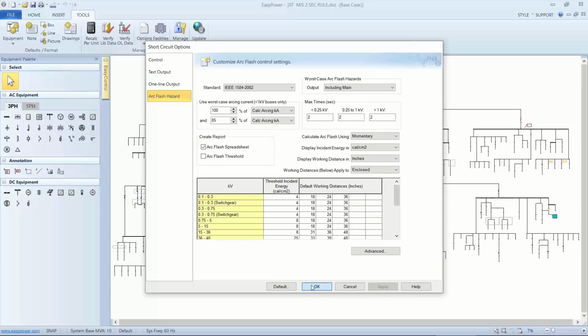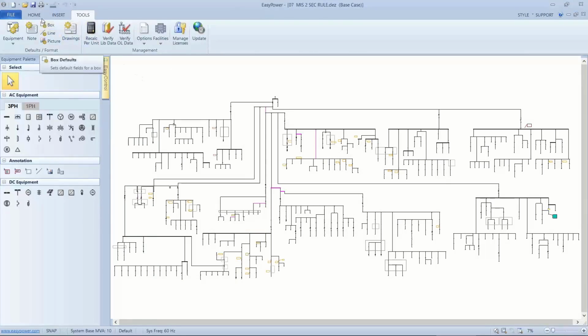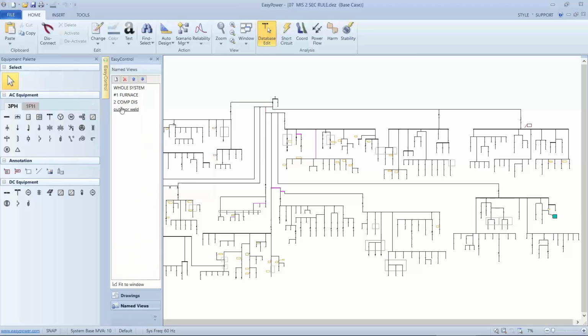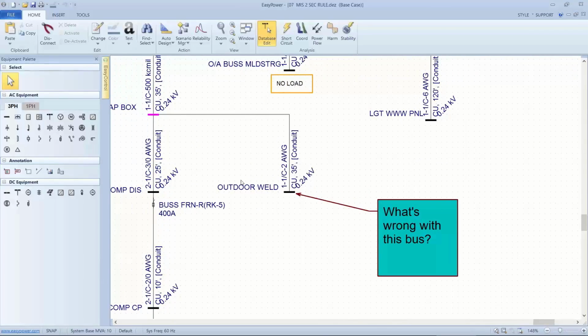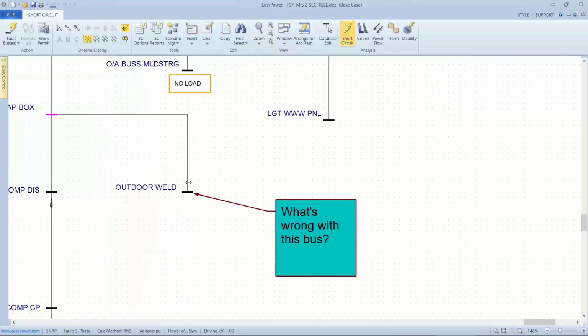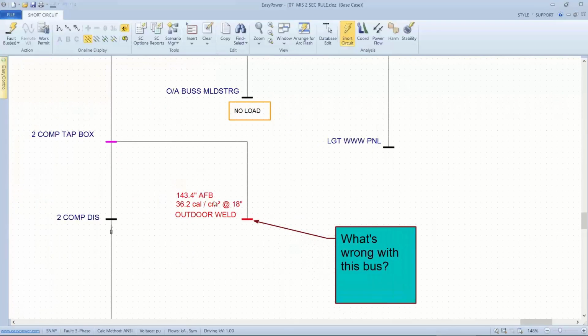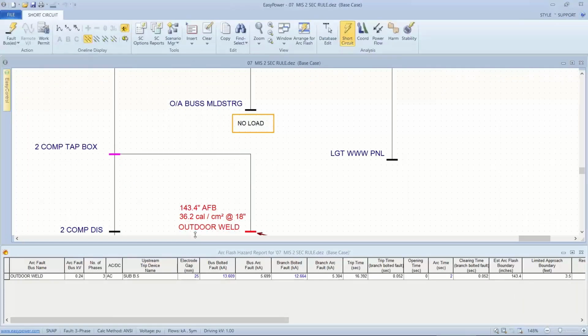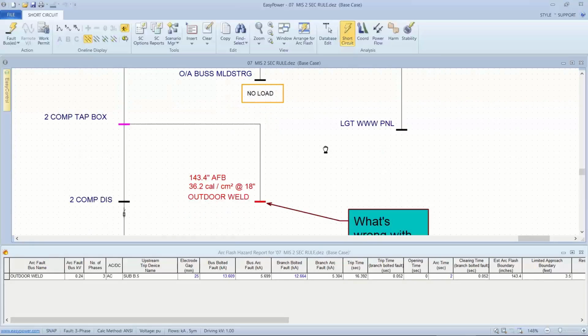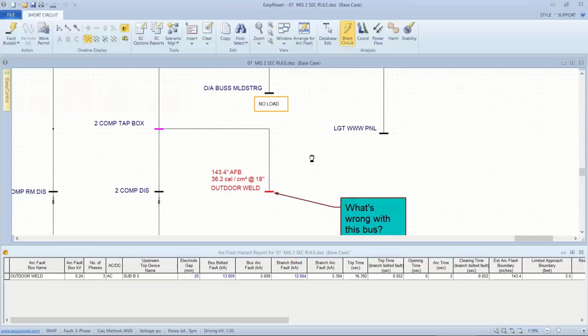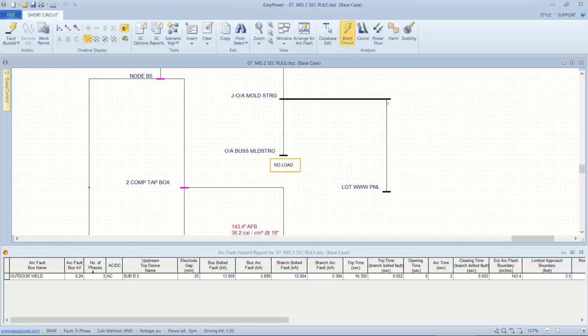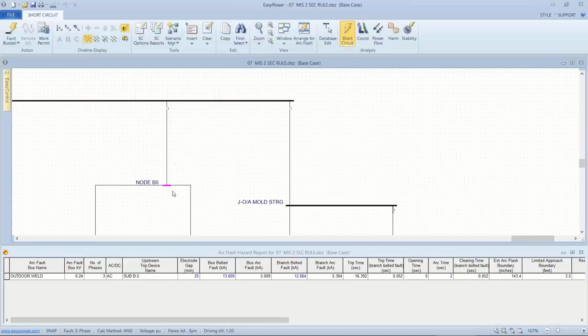Well, if we look at the distribution of the results, this has had the following effect. So here's a bus. If I go into short circuit focus and fault this bus, this is a 240 volt bus, I get a 36 calorie exposure even with the 2-second limit. That's dangerous in anybody's book. What's going on? Well, if I look at my arranged for arc flash display, I see that I have a bus fault current that's relatively dangerous, a branch fault current, and still I'm limiting the time to 2 seconds. What's right about this picture? And the following question is, what's the protective device involved? According to this, it should be sub B5, which is a breaker up here on the main bus.